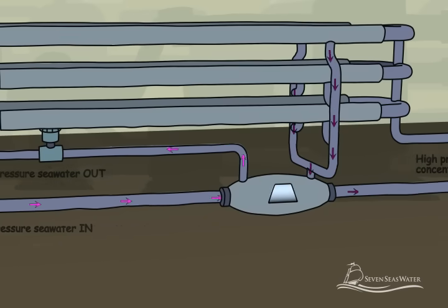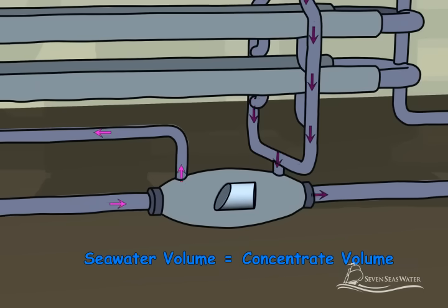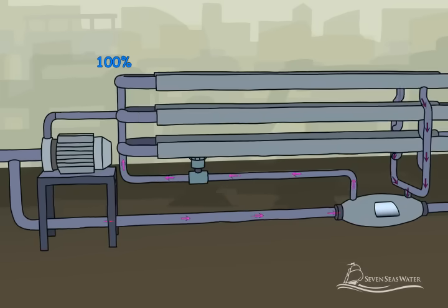Here, up to 98% of the energy of the concentrated salt stream is transferred to an equal volume of the incoming seawater in an isobaric energy recovery device. The energy recovery device significantly reduces the plant's operating costs by recovering the concentrated salt stream energy and using it to pressurize 60% of the seawater that is fed to the membranes.